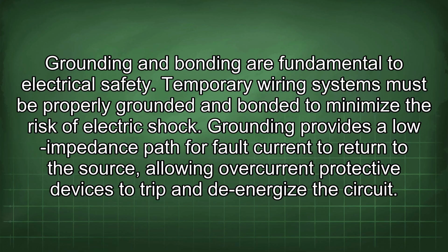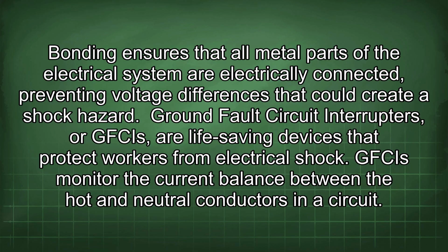Grounding provides a low impedance path for fault current to return to the source, allowing overcurrent protective devices to trip and de-energize the circuit. Bonding ensures that all metal parts of the electrical system are electrically connected, preventing voltage differences that could create a shock hazard.